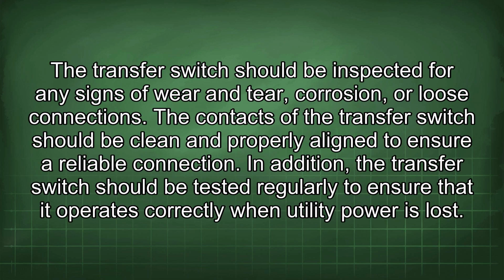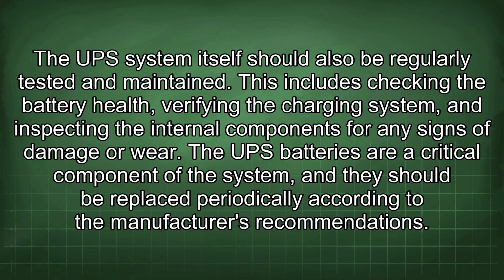The transfer switch should be inspected for any signs of wear and tear, corrosion, or loose connections. The contacts of the transfer switch should be clean and properly aligned to ensure a reliable connection. In addition, the transfer switch should be tested regularly to ensure that it operates correctly when utility power is lost. The UPS system itself should also be regularly tested and maintained.